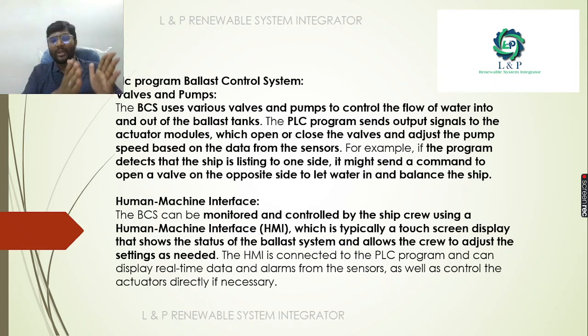Say, for example, if the program detects that the ship is listing to one side, it might send a command to open a valve on the opposite side to let the water in and balance the ship. Next, we use HMIs with a touchscreen display for the ship crew, so that they will know the exact status of the ballast system, which allows the crew to adjust the settings as needed.